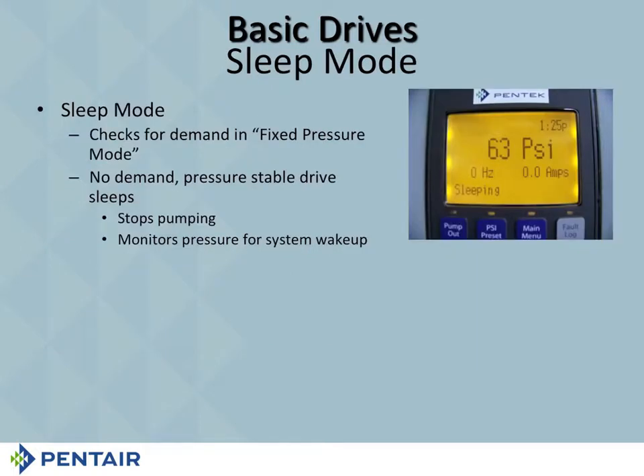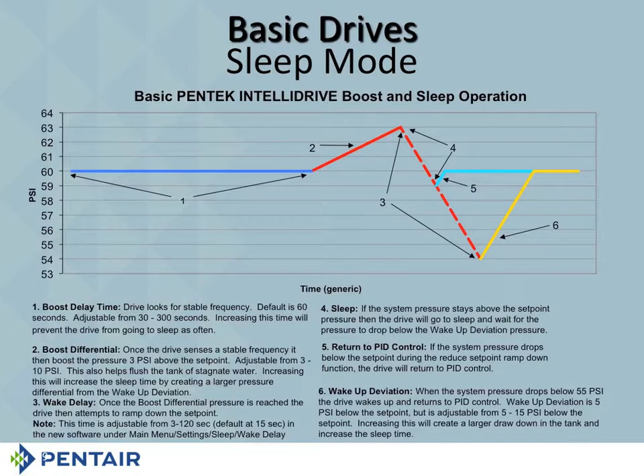Now, sleep. With sleep, what we do, and the main thing I'm showing you here, is we boost the pressure 3 psi, and when the pump goes to sleep, it says sleeping. So all it means is we've turned it off because we don't need it right now. So you're at 0 hertz and 0 amps, okay? Your sleeping mode looks like this, okay? Number one is a boost delay. Boost delay means that we're running at the same pressure and the same hertz for 1 minute. So let's see if we need to go to sleep.